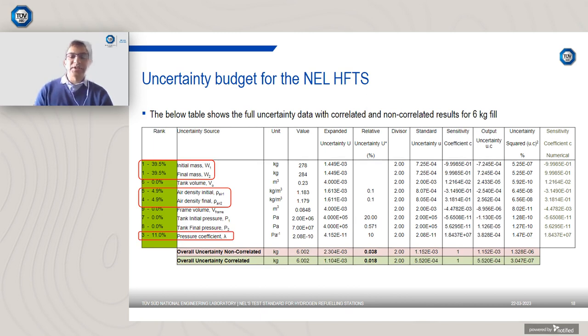The next slide shows the impact if you were to have a 6 kilogram fill, which is the maximum capacity for the test standard. In this case, again, the mass reading has the largest impact on the uncertainty. However, what you also find is that the pressure coefficient, which is used to calculate the tank expansion, also has a reasonable impact on the uncertainty. The reason for this is that when you pressurize the tanks to 700 bar, the tanks do expand quite a bit and therefore affect the overall uncertainty budget.